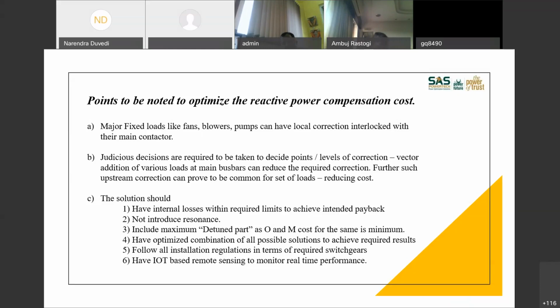These days, you can as well add IoT-based remote sensing to monitor real-time performance because, as I said, real-time power factor is becoming more and more important. So you can have a meter with SIM card based hardware inside the APFC panel, which will monitor your main incomer as well as panel performance, and you can keep getting feedback from that panel continuously on your mobiles from the cloud. So you don't invest anything in local hardware, and you can program those alerts and act on them so that bills are optimized. So this is also possible at not a very exorbitant extra cost.